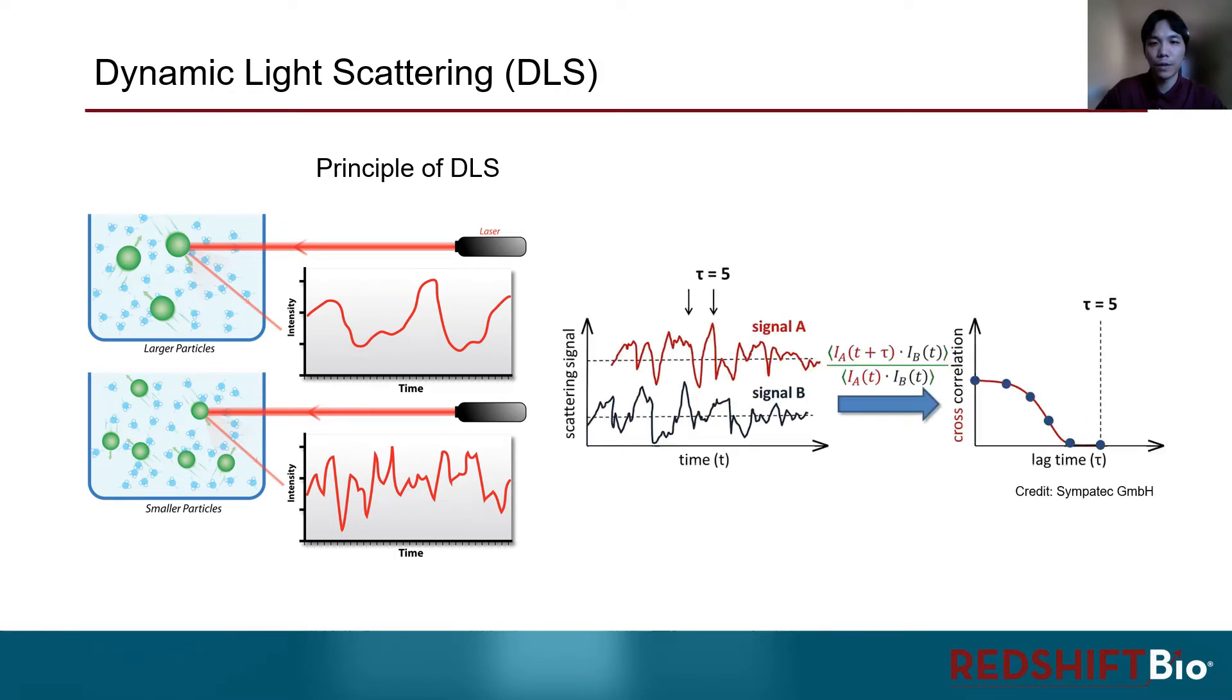So now, how do we use this information to calculate the size of the particles? In DLS, the snapshots of the scattering signals are taken rapidly one after another and compared back to the original signal, which is signal B in this example. Between each snapshot, usually within nano to microseconds, the signals are always pretty similar and well correlated. But as the delay time gets sufficiently larger, the similarity of the signals begin to decrease, and eventually, there will be no more correlation with the original signal.